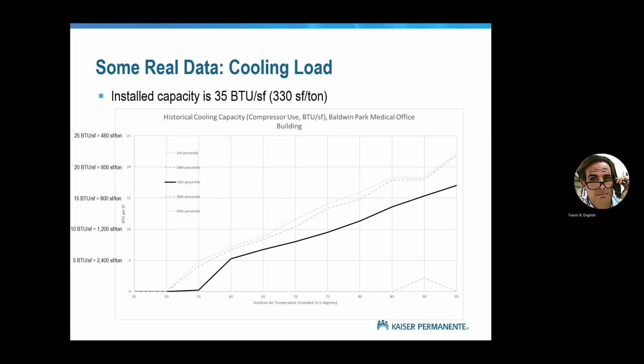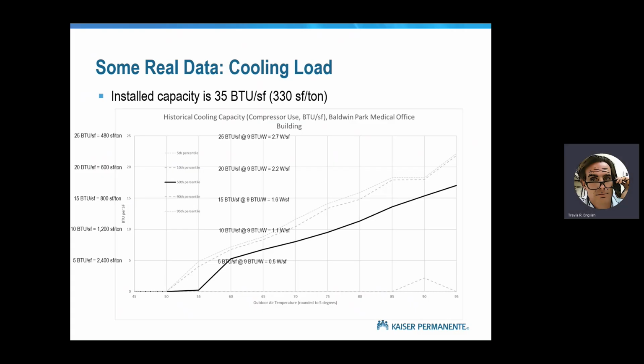Okay. So what does that look like in watts per square foot? Remember the number that we had in our head was 0.8 watts per square foot. So to convert the load to the energy, you use EER. The units on EER are BTU per watt. So if we assume a 9.0 EER on this cooling load, we can see where that comes in. And that 0.8 watts per square foot number that you have written down on your napkin means that we should be tracking somewhere in the neighborhood of 7.5 BTU per square foot or 1,500 square foot per ton as kind of our annual average, which is pretty good, right? That number's pretty good.